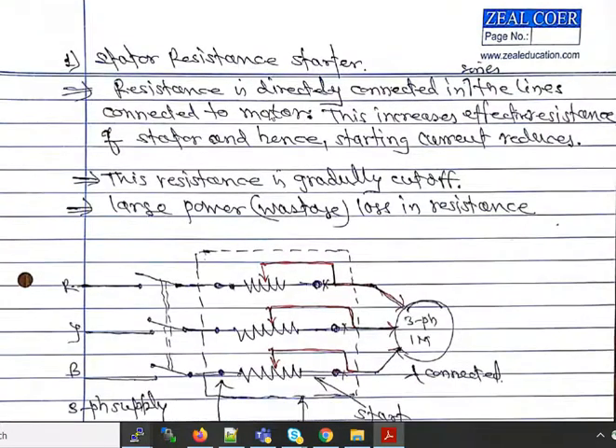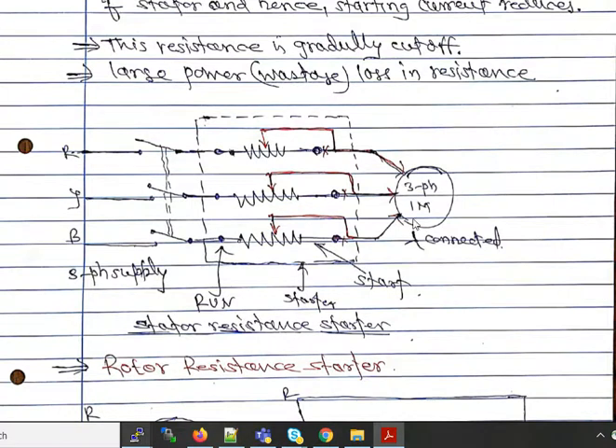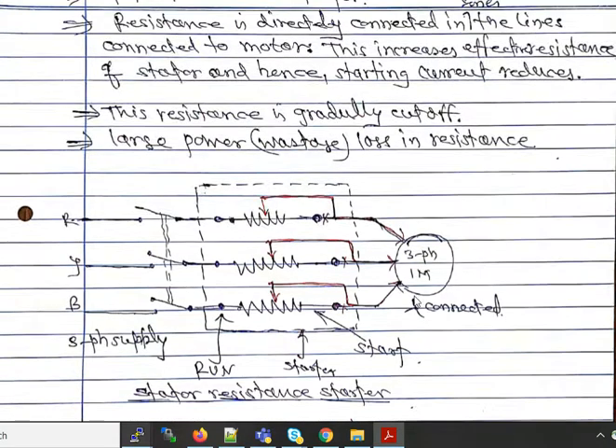In the stator resistance starter, resistances are directly connected in series with the supply lines to the motor. This increases the effective resistance of the stator and reduces the starting current. The resistance is gradually cut off as the motor accelerates. At the start position, the full resistance is in the circuit; at the run position, resistance is fully removed and full voltage is applied. However, this method is generally not preferred due to large power wastage in the resistances.